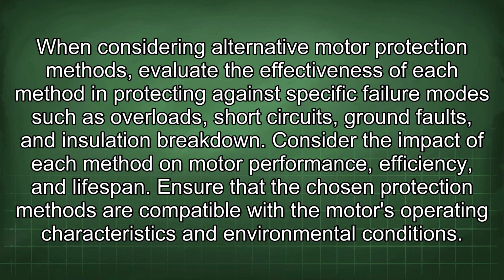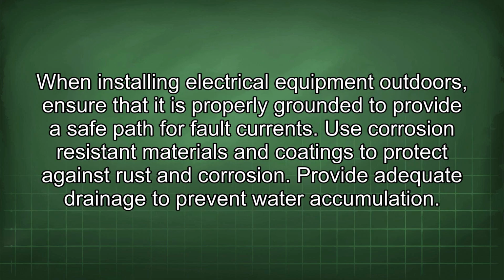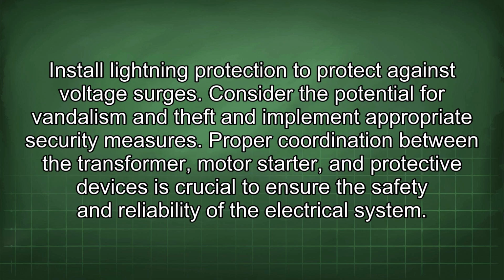Ensure that the chosen protection methods are compatible with the motor's operating characteristics and environmental conditions. When installing electrical equipment outdoors, ensure that it is properly grounded to provide a safe path for fault currents. Use corrosion-resistant materials and coatings to protect against rust and corrosion. Provide adequate drainage to prevent water accumulation. Install lightning protection to protect against voltage surges. Consider the potential for vandalism and theft and implement appropriate security measures.